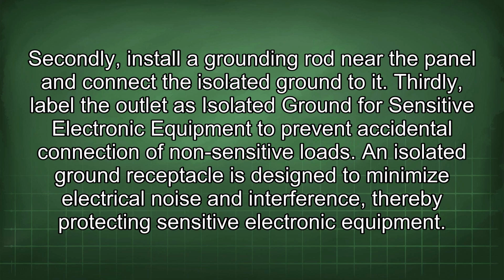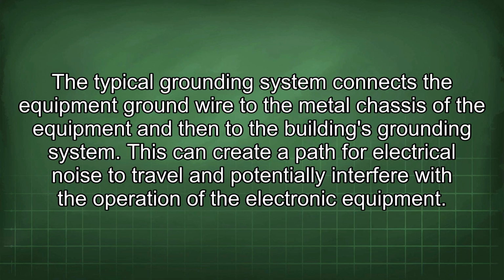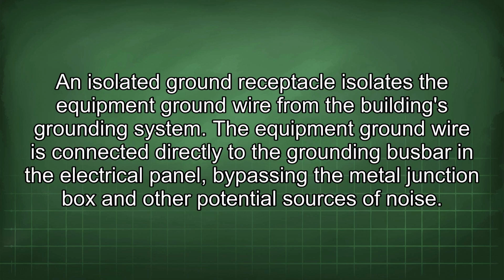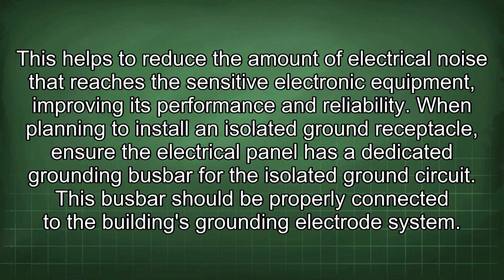An isolated ground receptacle is designed to minimize electrical noise and interference, thereby protecting sensitive electronic equipment. A typical grounding system connects the equipment ground wire to the metal chassis of the equipment and then to the building's grounding system. This can create a path for electrical noise to travel and potentially interfere with the operation of the electronic equipment. An isolated ground receptacle isolates the equipment ground wire from the building's grounding system. The equipment ground wire is connected directly to the grounding busbar in the electrical panel, bypassing the metal junction box and other potential sources of noise. This helps to reduce the amount of electrical noise that reaches the sensitive electronic equipment, improving its performance and reliability.